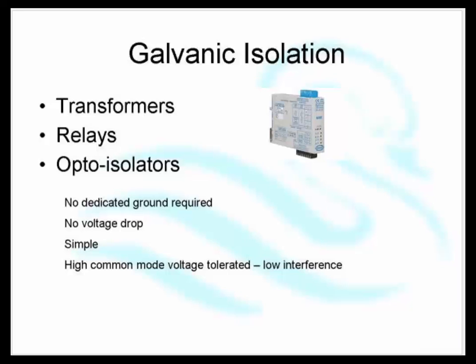They are more expensive. I know a lot of places now where they have an active policy. They go in and every time they have a shutdown, they change 5 of the Zeners for 5 galvanics. Just because it gives them a better sense of security. And, you know, if they were scheduled to test the damn things anyway, they probably would have ended up blowing. Price difference.